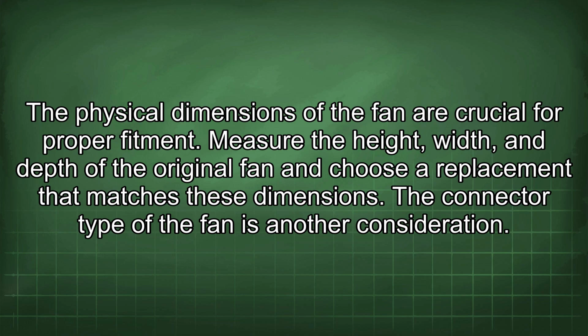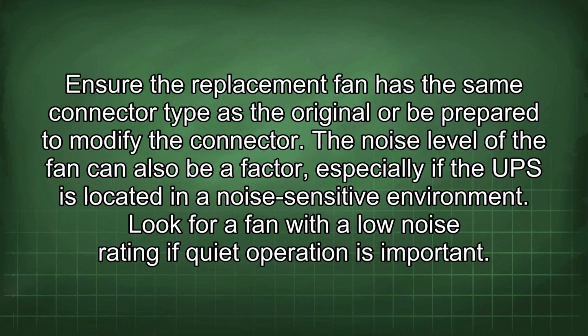The connector type of the fan is another consideration. Ensure the replacement fan has the same connector type as the original or be prepared to modify the connector. The noise level of the fan can also be a factor, especially if the UPS is located in a noise-sensitive environment. Look for a fan with a low noise rating if quiet operation is important.